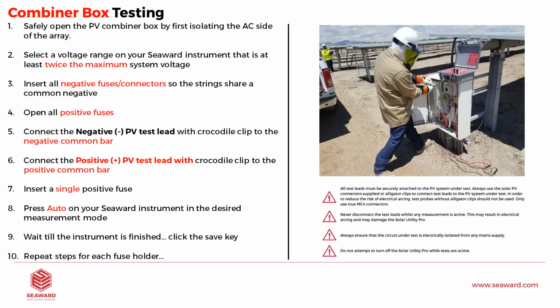So then we take the fuse that we kept with us and we put it inside the first fuse harness. We close it. We now have that string or whatever's connected to that fuse. That is then connected to our instrument. We should then see voltage on the instrument. We can push test. We wait for the test to run, doesn't take long. We push save. Open the positive fuse, take out the fuse, put it in the next harness, close, test.